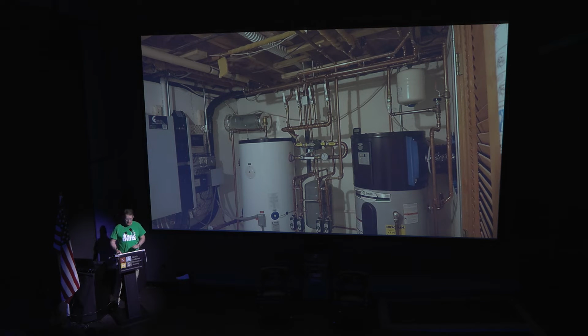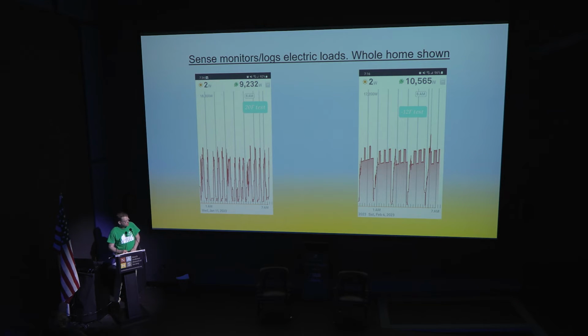So I'm going to switch gears a little bit and let's take a look at the electricity loads that this equipment needs, which will vary based on how cold it is outside. So here it's 20 degrees outside, and here's the signature of the whole house. Every load, every electrical need in the house is sort of peaking this way, but because the heat pump itself is such a big load, there's very little going on in the house at 1 a.m. So you can see a big spike for the heat pump to operate to make it warm inside when it's 20 Fahrenheit outside.